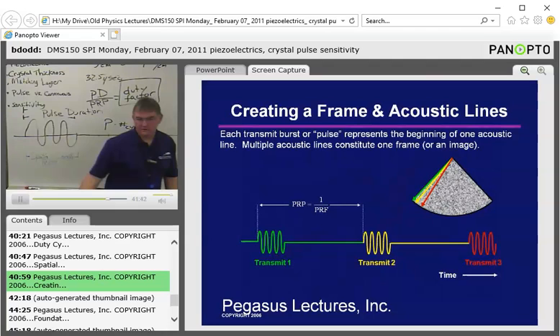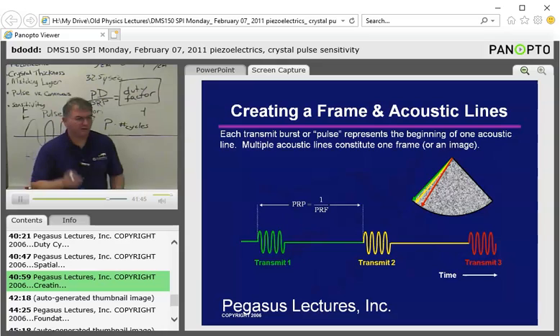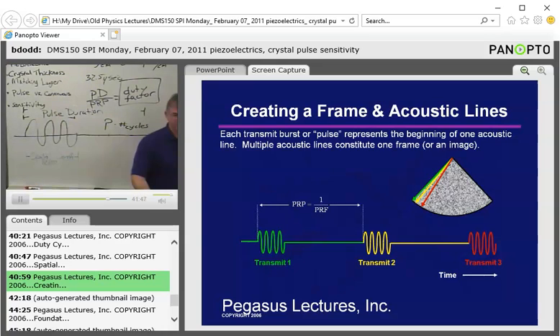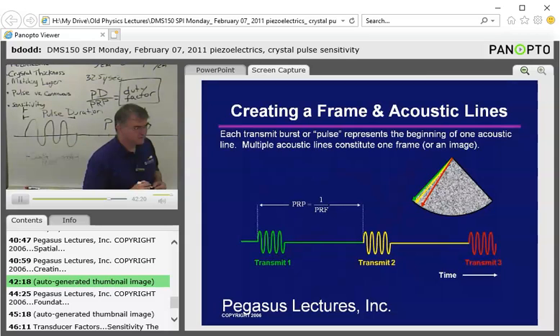I move over one spot. I send out a pulse. I get 1 echo back. I move over another spot. I get 3 echoes back. Each time I'm sending out a pulse. Then I come over and I send out a pulse. I don't get any echoes back. That's fine. We leave that part blank. We come over here. We send out a pulse. We get 4 echoes back. Okay, so you see how I'm making an image of the room in a sector shape as I go around and send out a pulse and wait for the echoes to come back. So for each line of scanning, we get 1 pulse in the simplest model.